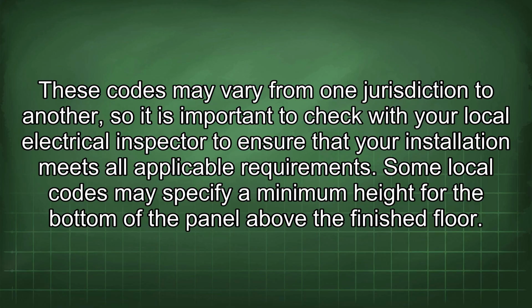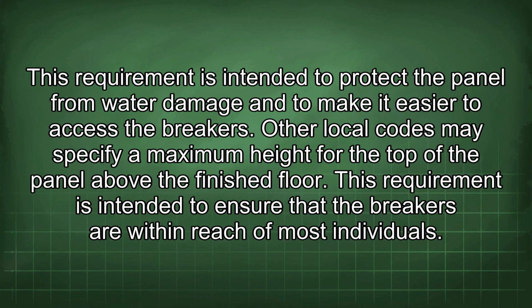Some local codes may specify a minimum height for the bottom of the panel above the finished floor. This requirement is intended to protect the panel from water damage and to make it easier to access the breakers. Other local codes may specify a maximum height for the top of the panel above the finished floor. This requirement is intended to ensure that the breakers are within reach of most individuals.